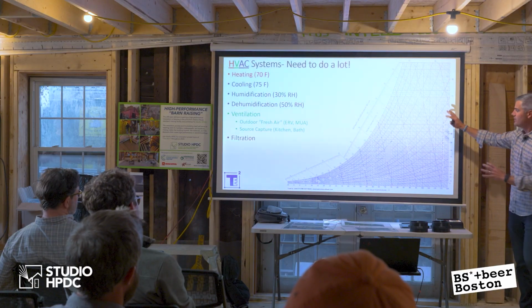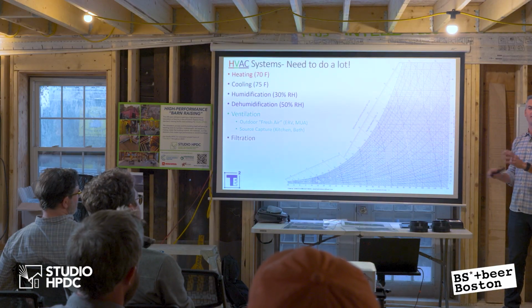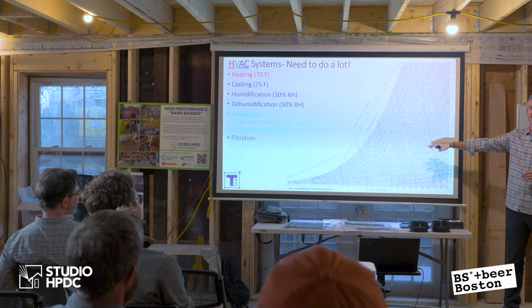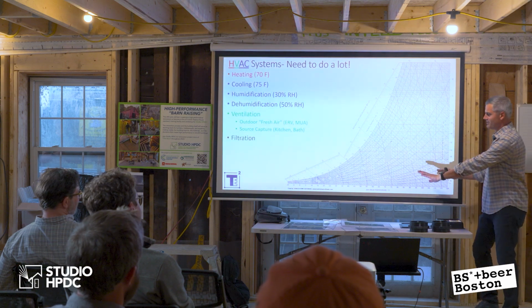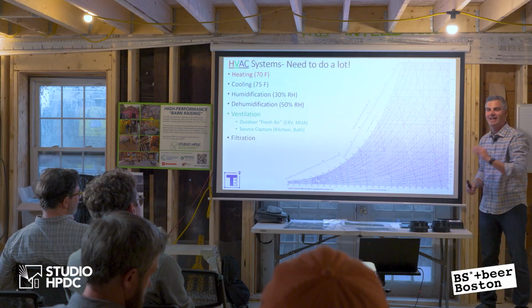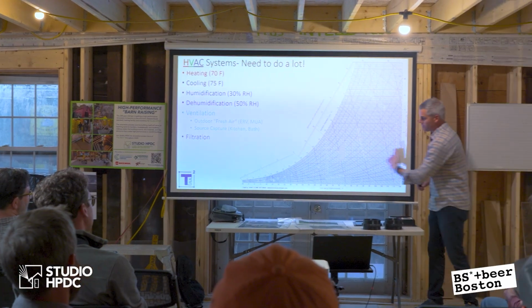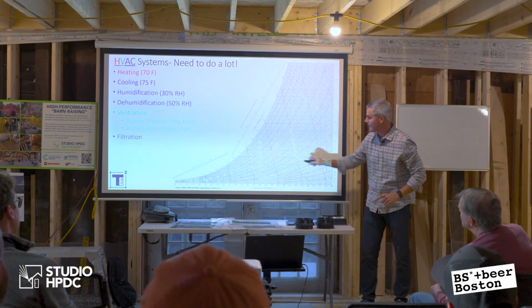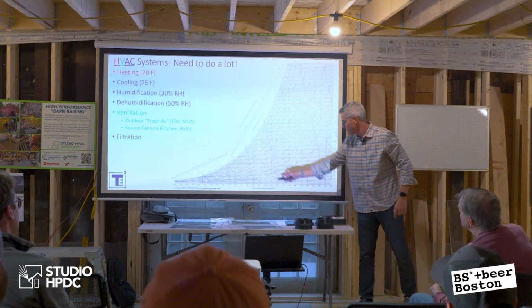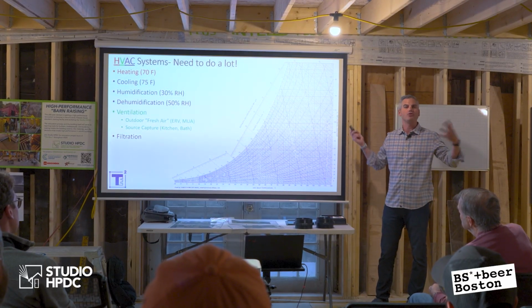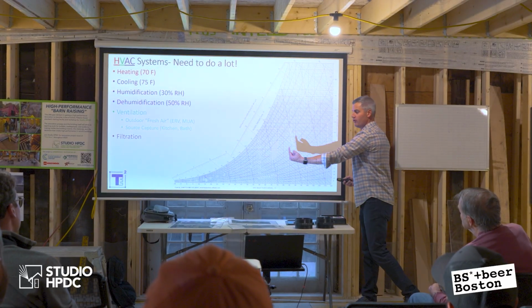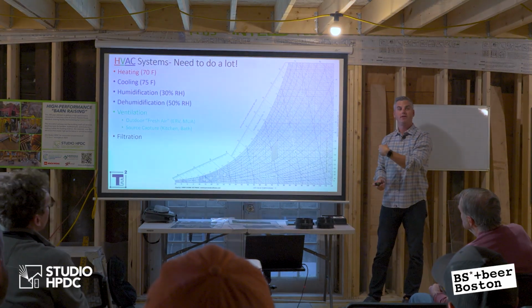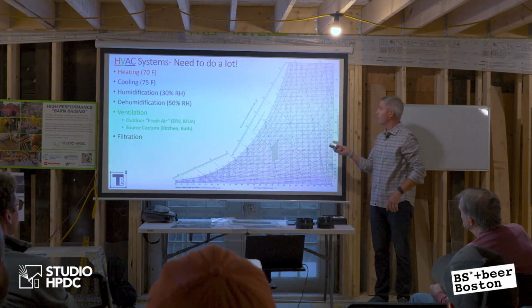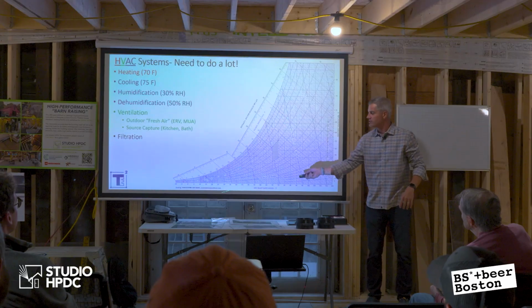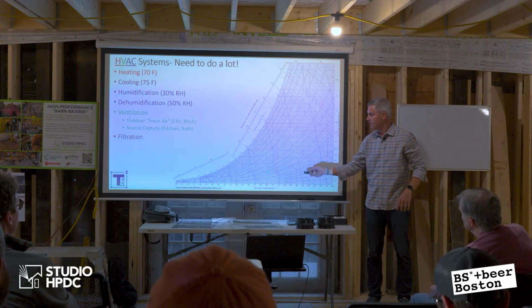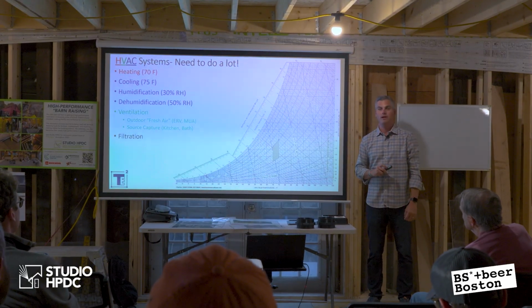So I'm gonna show you, I have a couple of technical slides. This is one, it's called the psychrometric chart, okay? So let me just explain this real quick. This is every condition that air could be at. If I move left, I'm colder. So in this example, that's minus 10. This is 120 degrees. So think about outdoor air temperature. Really cold over there, really hot over here. And then the y-axis is humidity. Really humid up here, really dry down here. 10% all the way to 100% humidity. Okay?